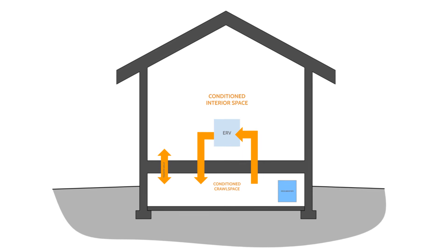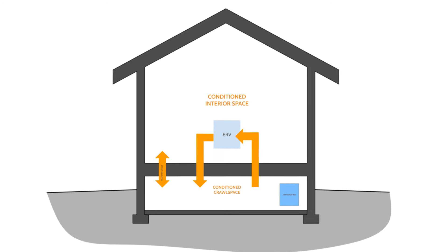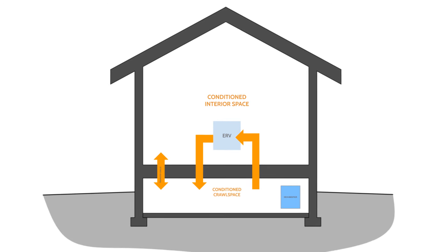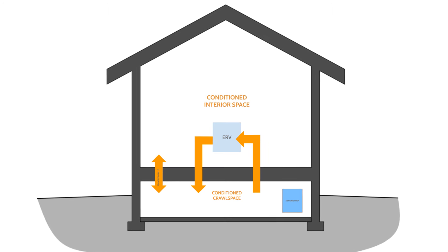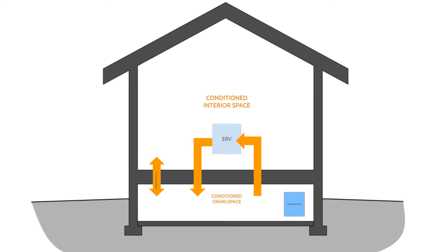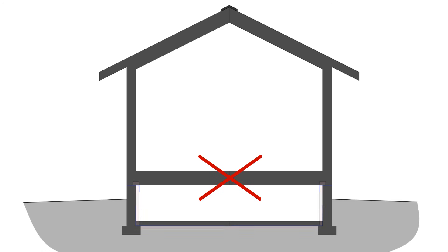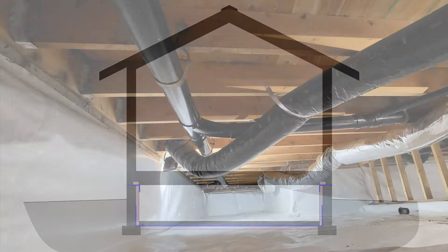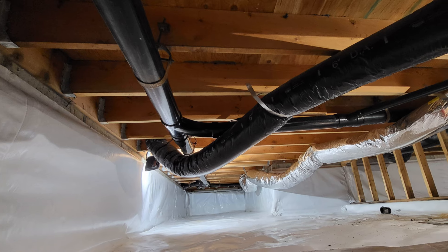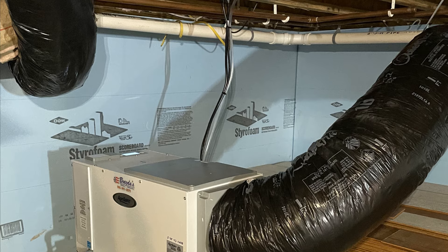A conditioned crawl space is part of the conditioned space. It receives fresh air and exhausts stale air, and it's pressure balanced with the interior living space with transfer grills or another strategy to reduce the chances of a negatively pressurized space. A conditioned crawl space is essentially a short basement and has to be treated like one — we aren't introducing any unconditioned outside air. Conditioned crawl spaces are insulated not at the floor level but rather at the exterior stem walls and at the rim joists, with supply and return ducts, transfer grills, or another means of air circulation provided within the space.